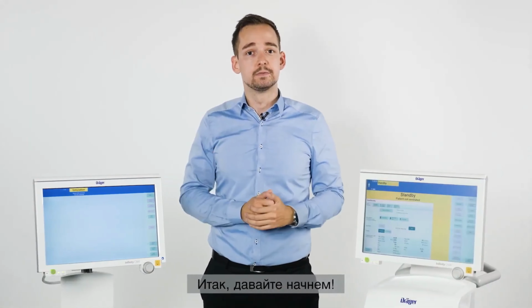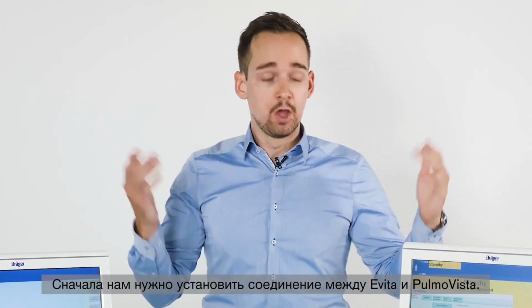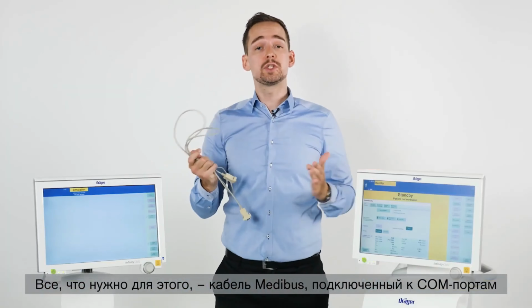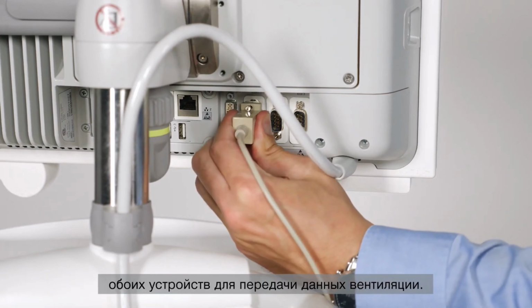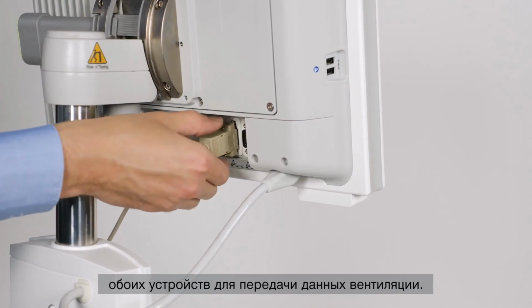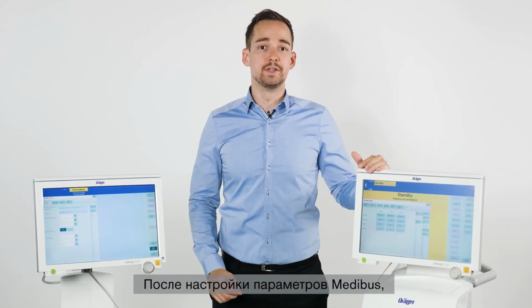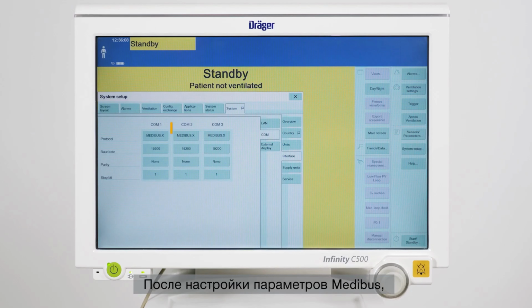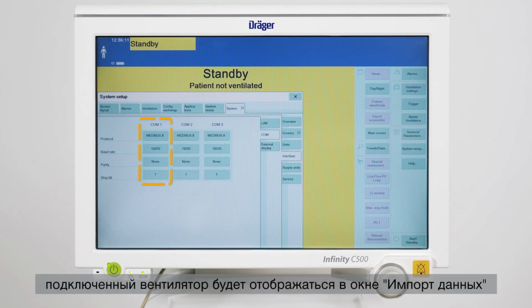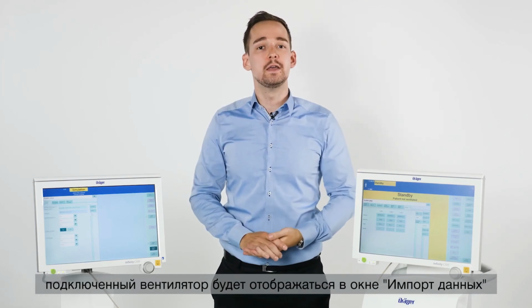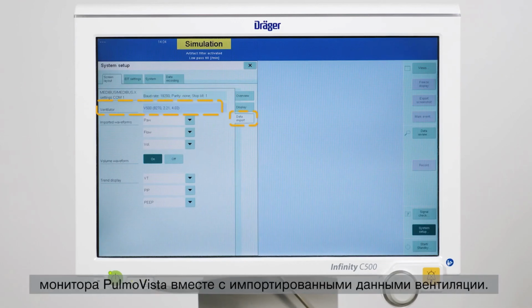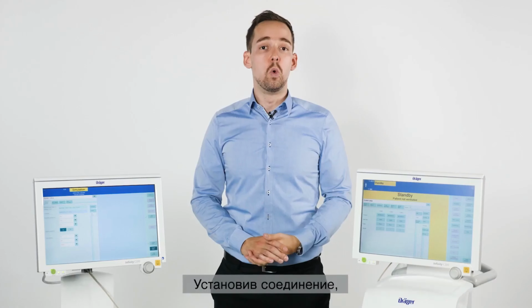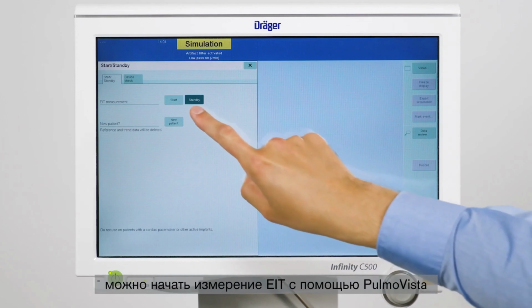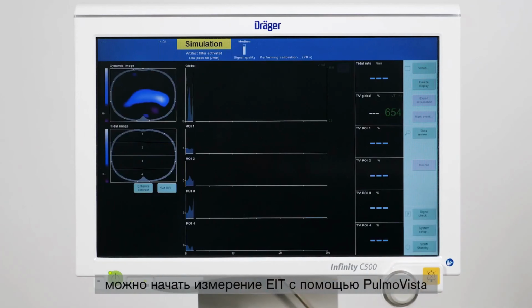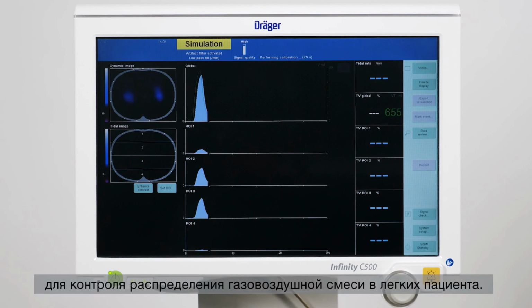So let's get started. First, we need to establish a connection between the Evita and PulmoVista. All we need is a Medibus cable, which is connected to the COM ports of both devices to transfer ventilation data. After setting the Medibus preferences of the ventilator to the following settings, the connected ventilator will be displayed in the data import window of PulmoVista together with the imported ventilation data. Once a connection is established, we can start an EIT measurement by PulmoVista to monitor the patient's ventilation distribution.